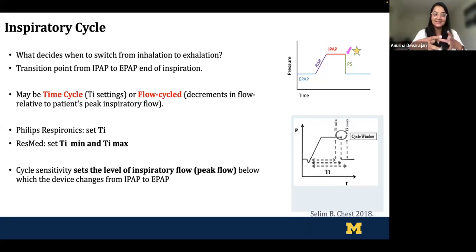So in cycle, the same thing comes into play as well, wherein is it a flow cycle, which is in all spontaneous breaths, wherein the machine senses a decrement in peak inspiratory flow and cycles out from the IPAP to the EPAP. But however, in the machine delivered breath, this inspiratory cycle depends on the time or the TI settings. Back in the past, Respironics was super easy and it never really got complicated because you set 1 TI and let them be. But however, in ResMed, we have this extra layer of complication wherein we set a TI min and we have to set a TI max.